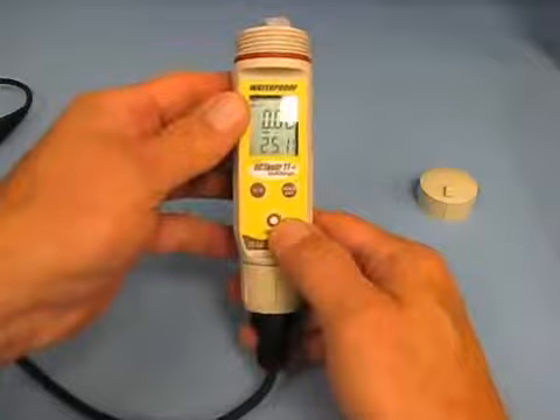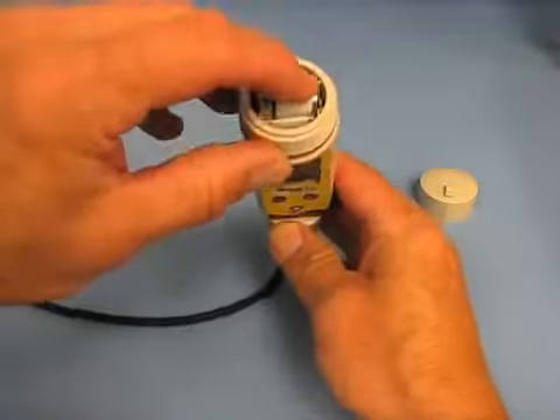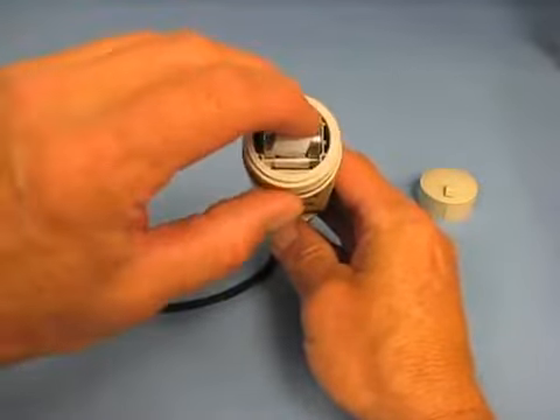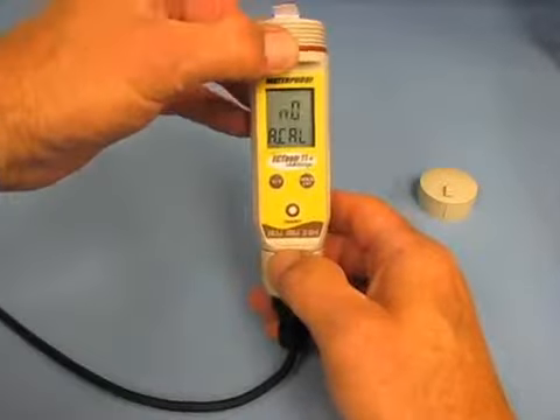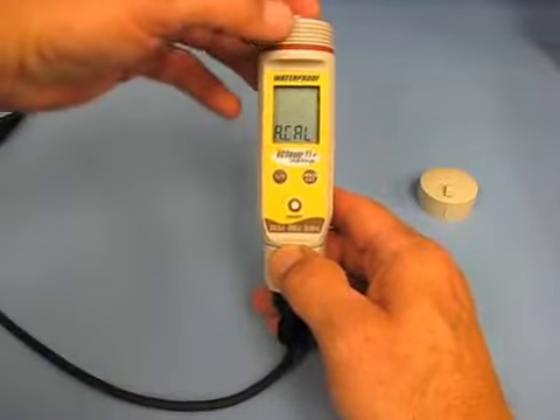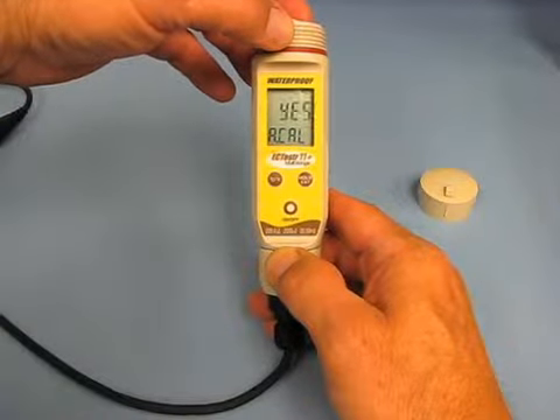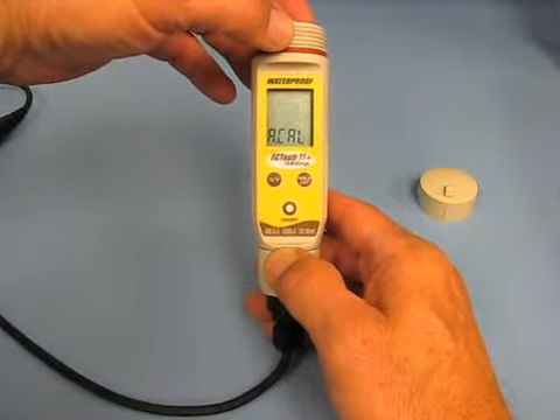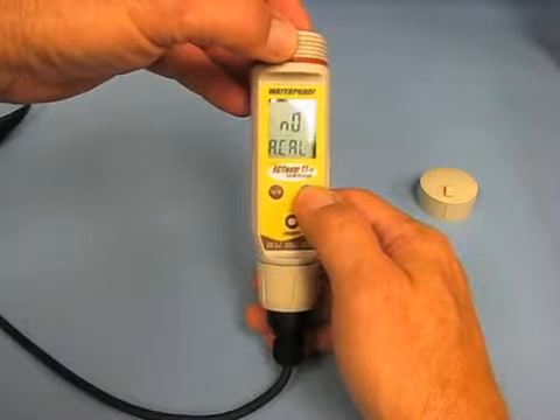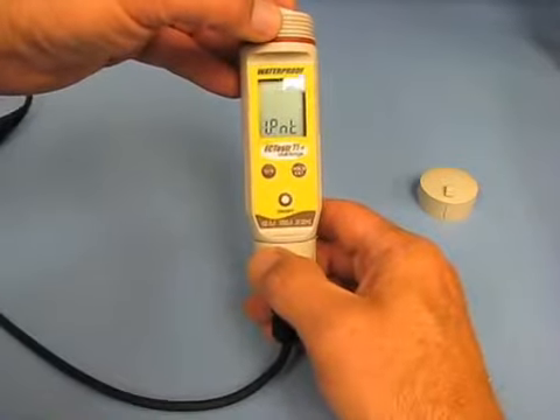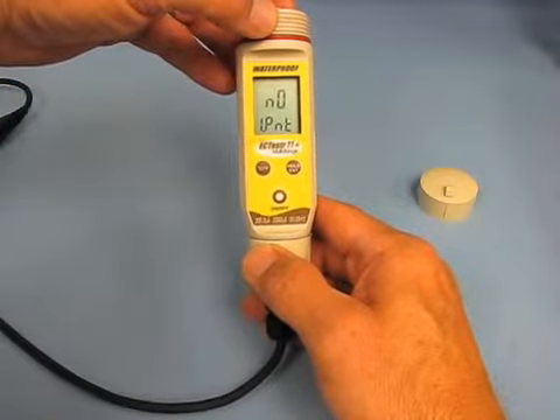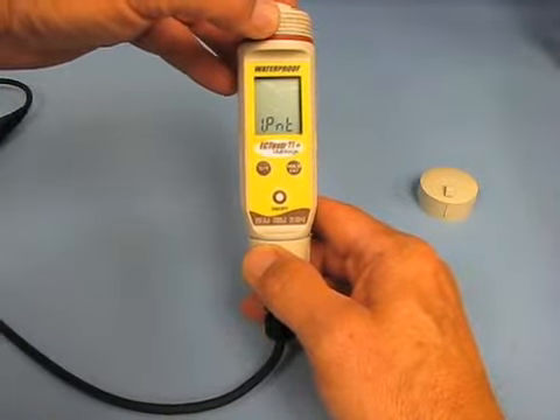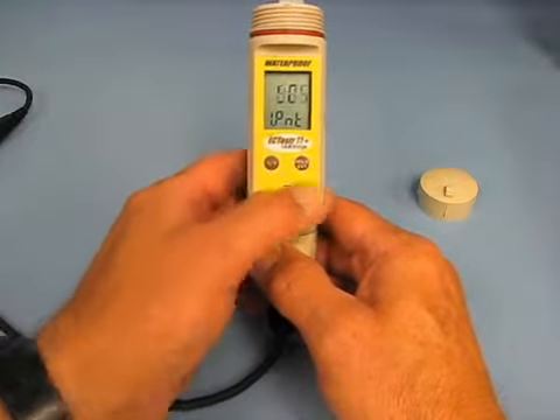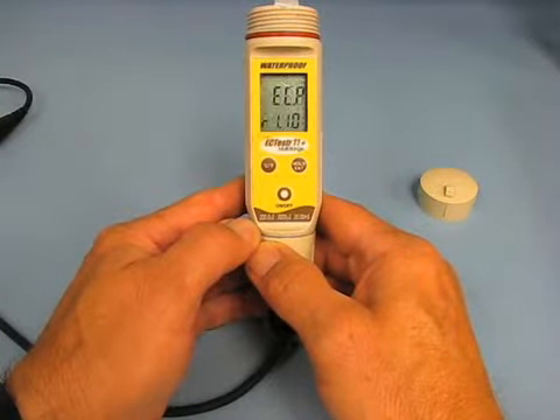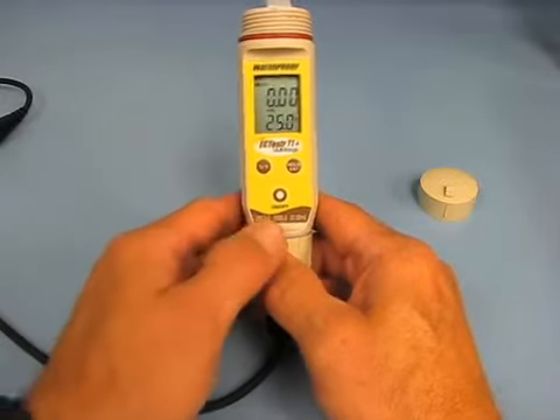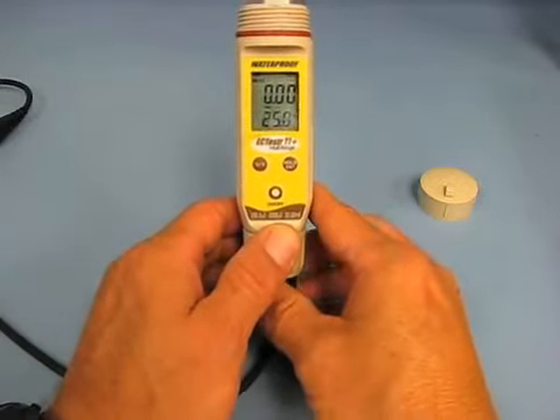Now if there's a chance that the meter was set up improperly, let's go through the steps again. Hold the increment button down, press on off, and then press the increment button again to change auto calibrate from yes to no. The increment button changes the features. You have to hit the enter key to accept that value. At 1-point calibration, no, or 1-point calibration, yes, you want it to be yes. And there you go. The meter is set up to be used as we described here, and hopefully have good luck with it.